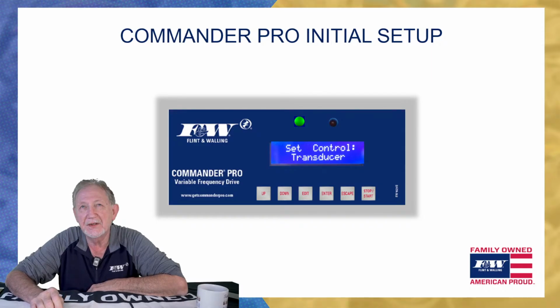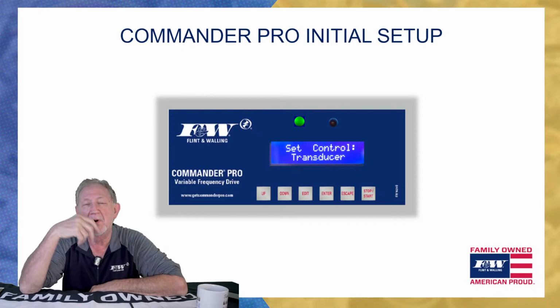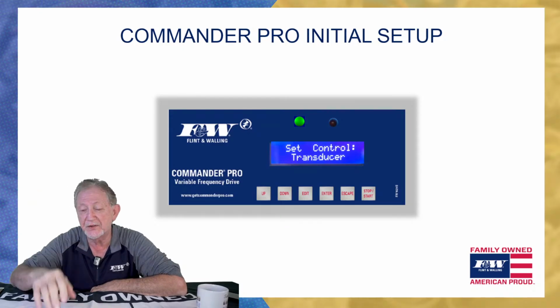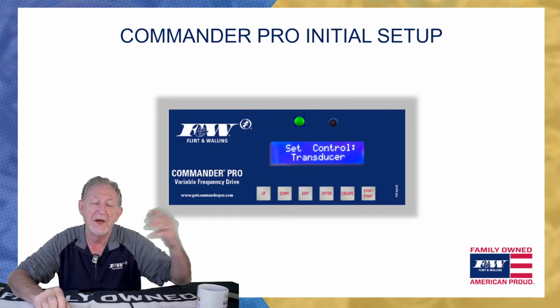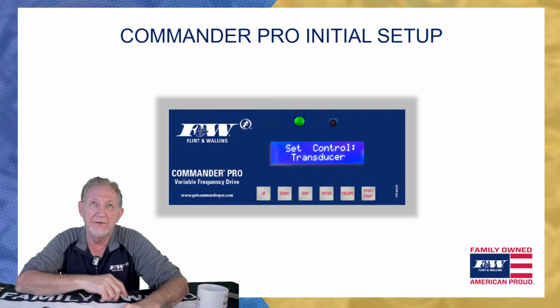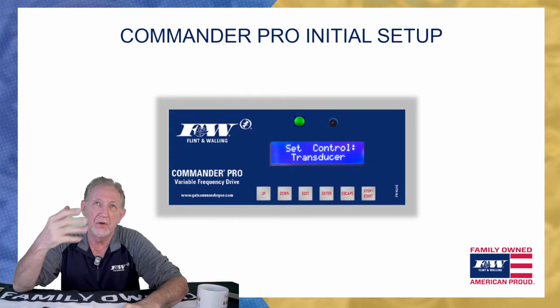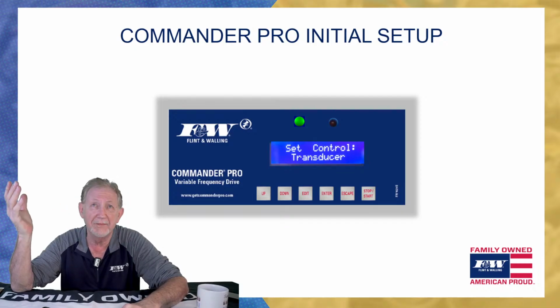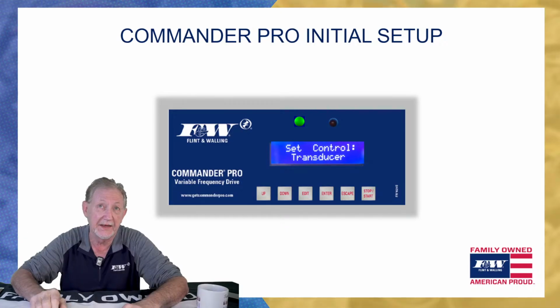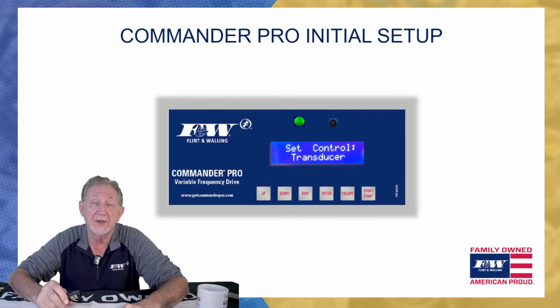And then this last thing we're going to set here is we're going to tell the drive, what are we using to turn the pump motor on and off? Is it a transducer, a pressure transducer, or is it a switch? Because this drive will operate off of either one, a transducer or a switch. If you select transducer, and I'm going to guess 95% of the time that's what's taking place, is we're selecting a transducer. That's what they're shipping out of here with.